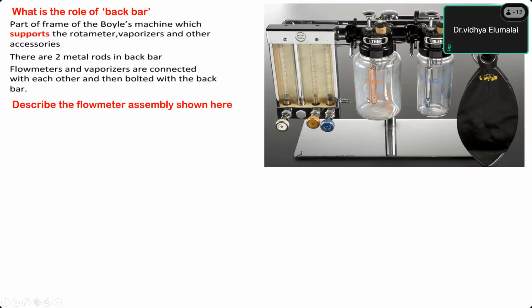It has oxygen, air, and nitrous oxide flow meters, where oxygen is separated from the other two flow meters. The second one is yellow colored. The next one has no knob at all. It is a silver tube. It is not a flow tube. There is no control knob here. And this is an orange colored knob, not air color. These are all standard color codes: oxygen white and nitrous oxide blue. But this is orange. It's not... cyclopropane, sir. Cyclopropane, excellent.